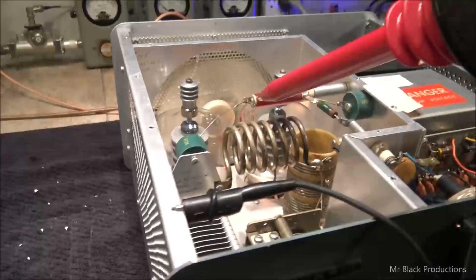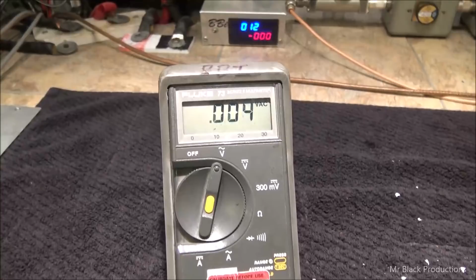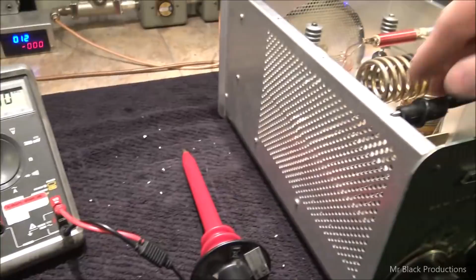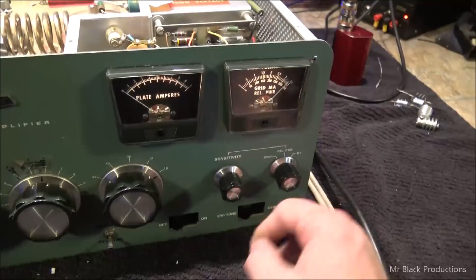There's no AC ripple coming past here. There's no measurable AC current whatsoever. And that little spike that we see when we come on and off, here, check it out, is we're measuring the actual electrostatic principle of change, the induction change between the contact of coming on, or coming off and coming on the probe point. So we got 0 AC leak, which is good. It means there's not going to be any hum. That means we're going to have a stable capacitor.